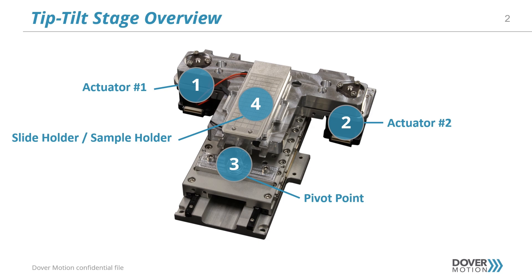Moving only actuator number one or actuator number two would provide a tilt or roll of the sample. Moving both actuators number one and two together would provide a tip or pitch of the sample with respect to the pivot point.